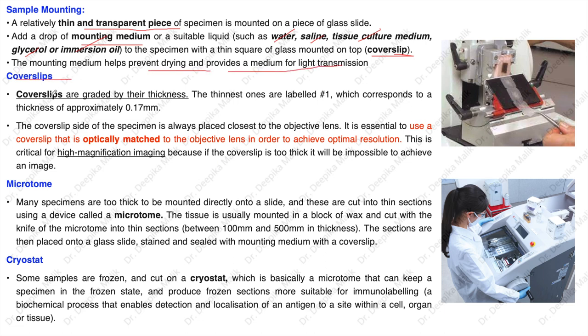Cover slips are graded by thickness; the thinnest are labeled as number one, corresponding to approximately 0.17 mm. The cover slip side of the specimen is always placed closest to the objective lens. It is essential to use a cover slip optimally matched to the objective lens to achieve optimal resolution. This is critical for high-magnification imaging, because if the cover slip is too thick, it will be impossible to achieve a clear image.